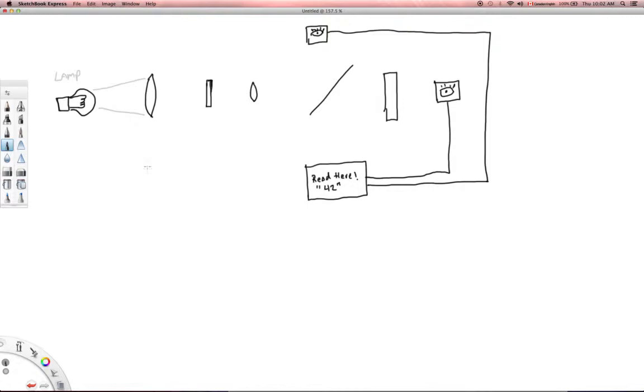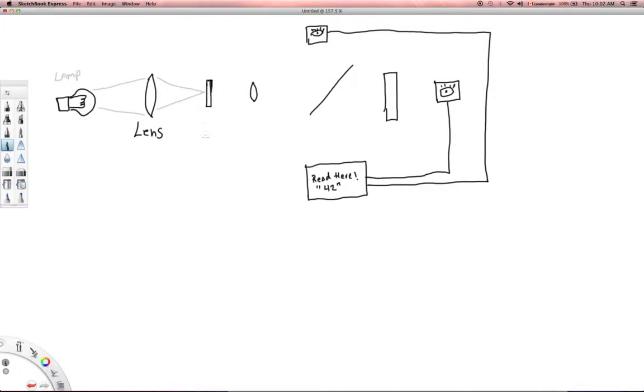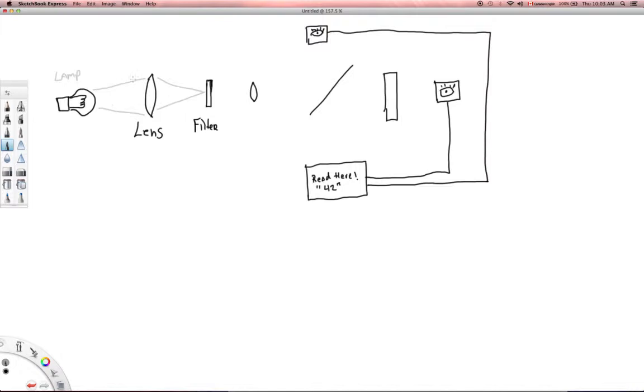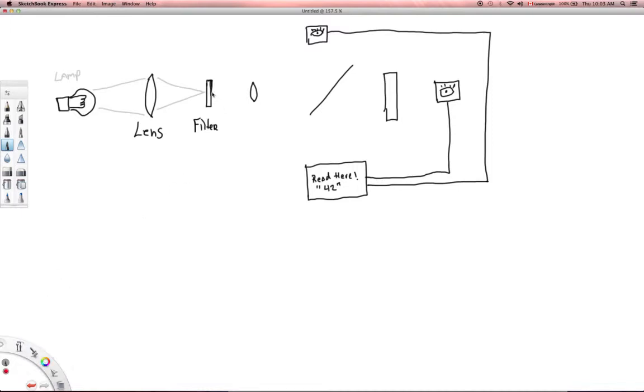All right, and this light is going to go through a lens here, and we're going to use this lens to focus the light. So there we go, boom, going through the lens, and then the light's going to get focused as it comes out of this lens here, and it's going to get focused on either a filter or probably a diffraction grating will be used. There's going to be some sort of filtering mechanism that filters out all of the wavelengths that we don't want and just uses the specific wavelength of light that we want.